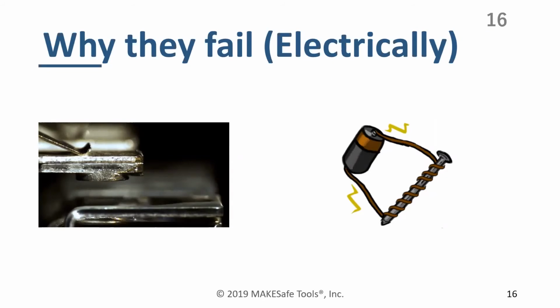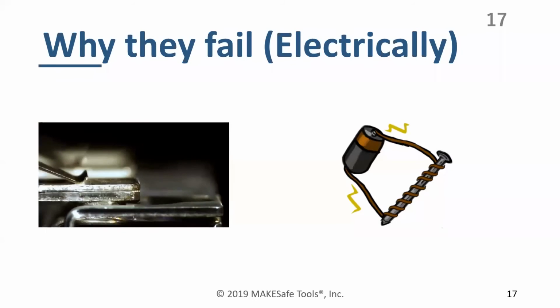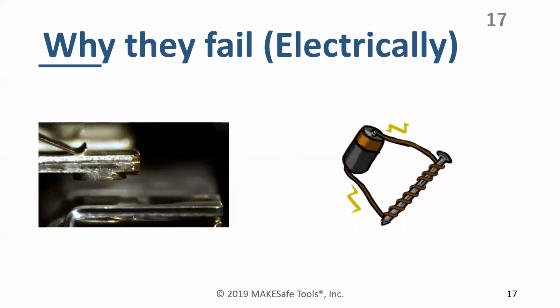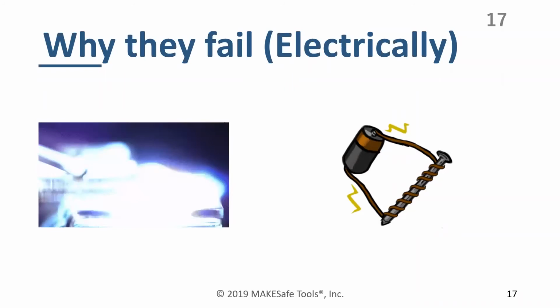When you're switching motors, they are a notoriously difficult load to switch, because any actual switch is just two pieces of metal that touch each other. That's what most switches are at their most basic point. But a motor, every time you disconnect it, does this—you see that welding arc flash? A reasonably loaded motor will do that every time you disconnect it, and you can imagine that's very destructive for switches.